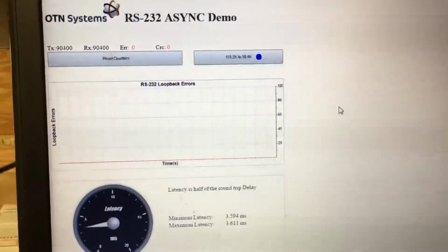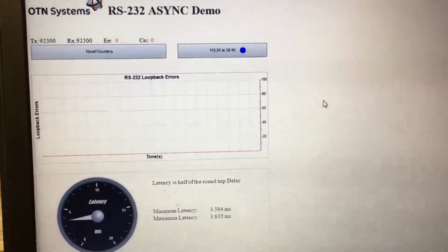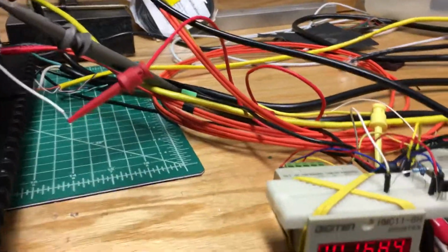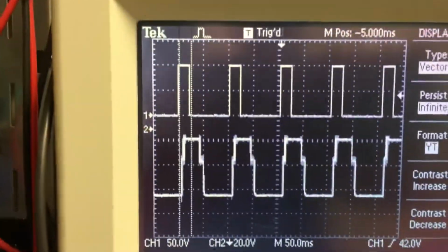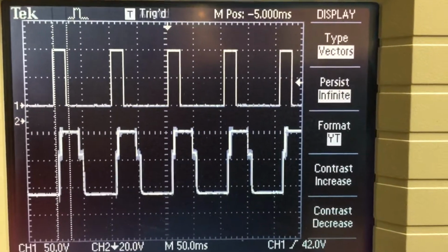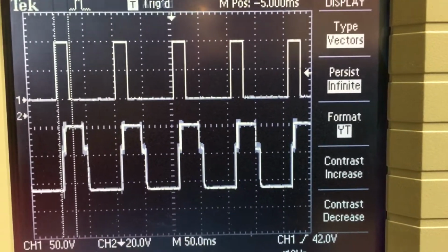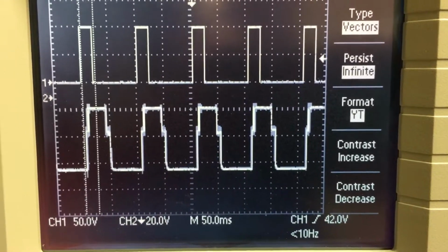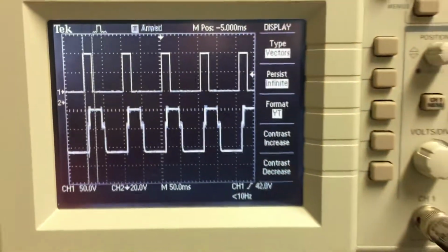We've done this 10 times. As you can see here, there's been absolutely no loss whatsoever. Same thing there, we're not losing anything. Before I slow it down, let's look at the persistent path. There's absolutely no shadow whatsoever. It looks like all the trips were sent. No missing, no delayed trips or anything like that.